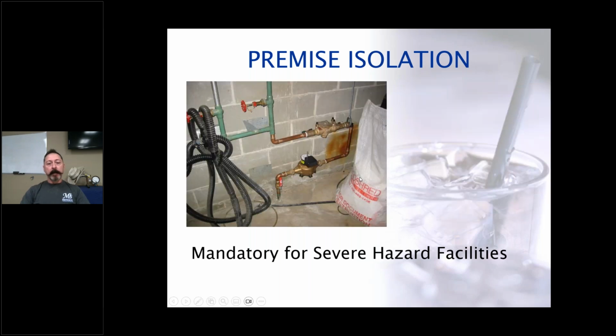So again, mandatory for severe hazard facilities. This is what a typical installation would look like. You'd have a shut off, a water meter if there was a water meter, and then you'd have a backflow preventer, which is that thing right there. And that's an RP. Usually there should be a drain and stuff underneath there. That's one thing we'll get into in a sec, but that isolates that building.